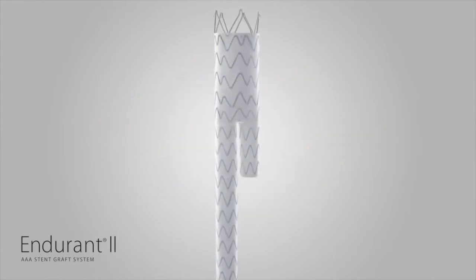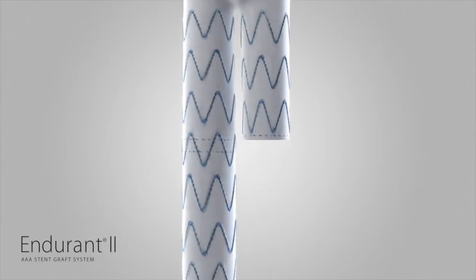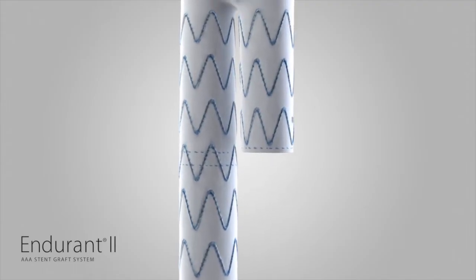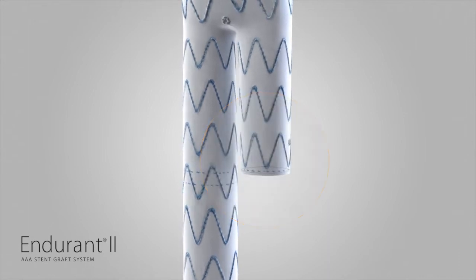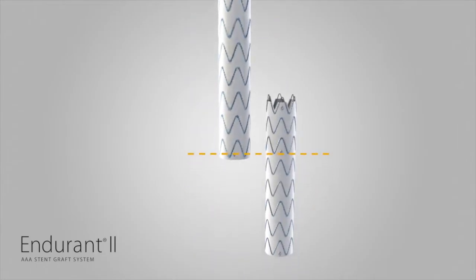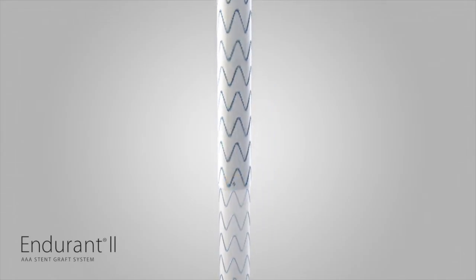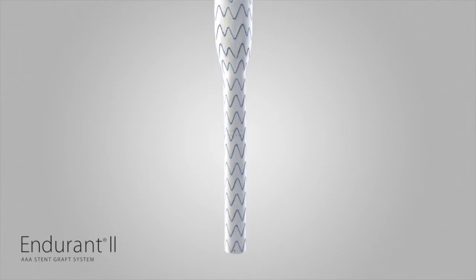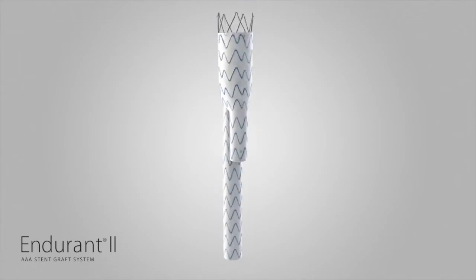Endurant II Enhanced Radiopaque Markers increase visibility for positioning the device and cannulating the gate. The contralateral gate marker is thicker and easier to see. In addition, all Endurant II contralateral limbs and iliac extensions have an overlap marker to aid with alignment of overlap between components. Lastly, the radiopaque marker on the bifurcated contralateral leg has been repositioned so that the marker is located in the true lateral position.